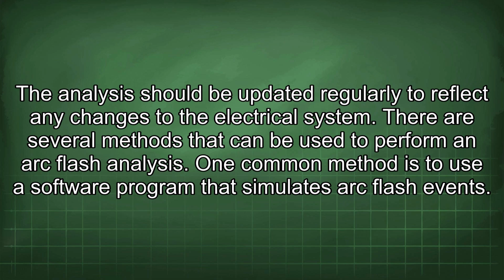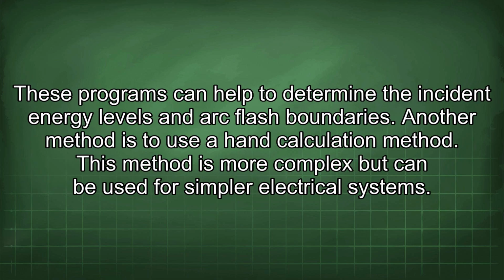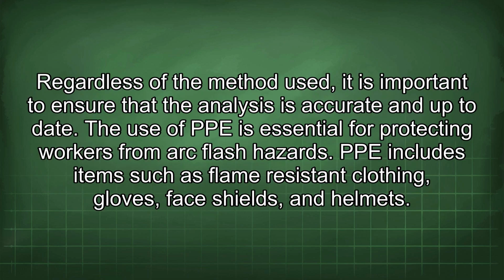There are several methods that can be used to perform an arc flash analysis. One common method is to use a software program that simulates arc flash events. These programs can help to determine the incident energy levels and arc flash boundaries. Another method is to use a hand calculation method. This method is more complex but can be used for simpler electrical systems. Regardless of the method used, it is important to ensure that the analysis is accurate and up to date.